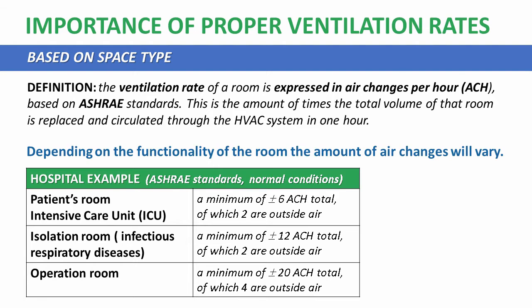For example, in a patient's room or an intensive care unit, we need at least 6 air changes an hour, of which 2 air changes should be outside air. For an isolation room, we need a minimum of 12 air changes an hour, of which 2 should be outside air. For an operation room, this is a lot higher: a minimum of 20 air changes an hour, of which 4 should be outside air.